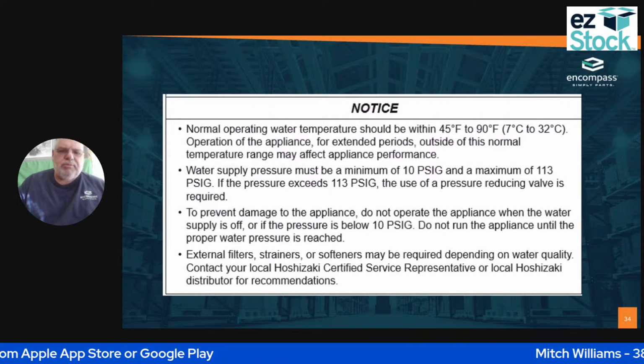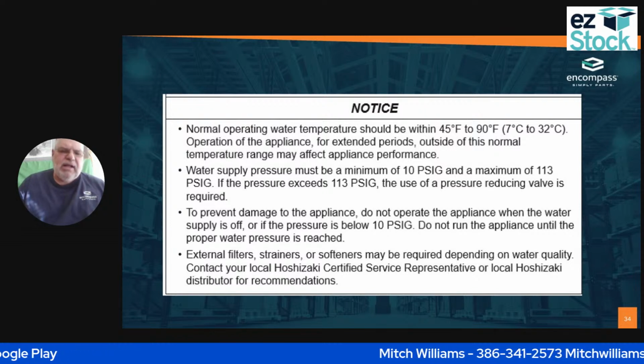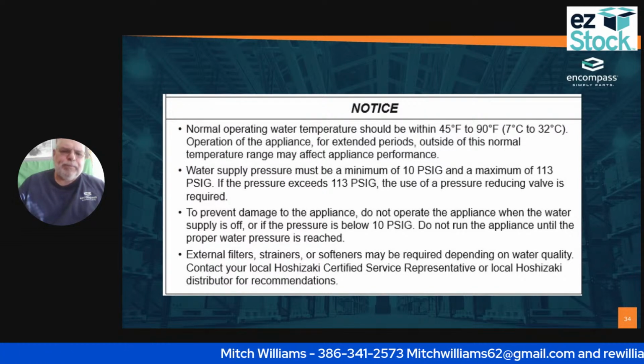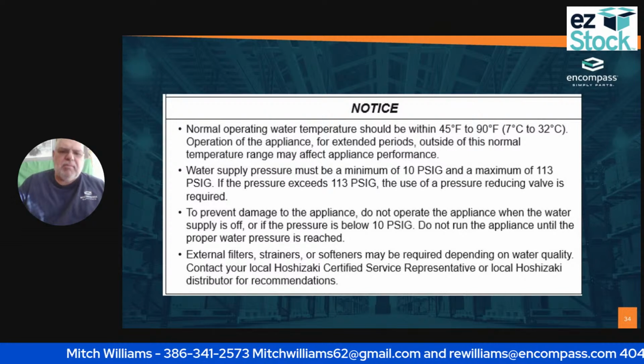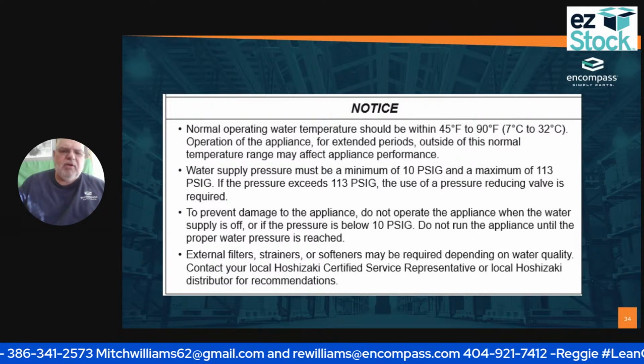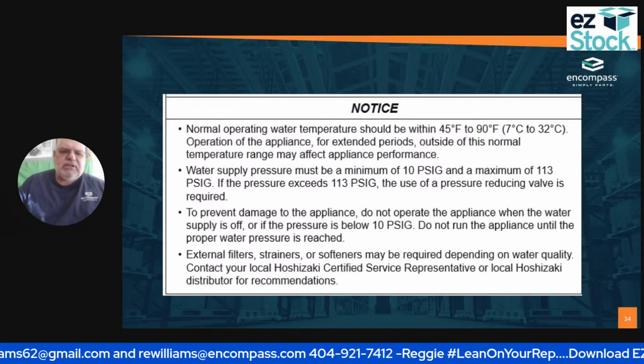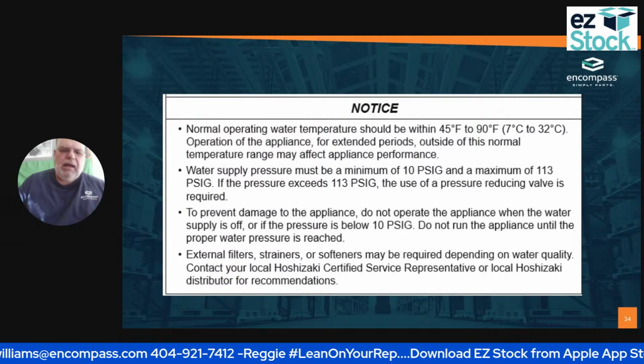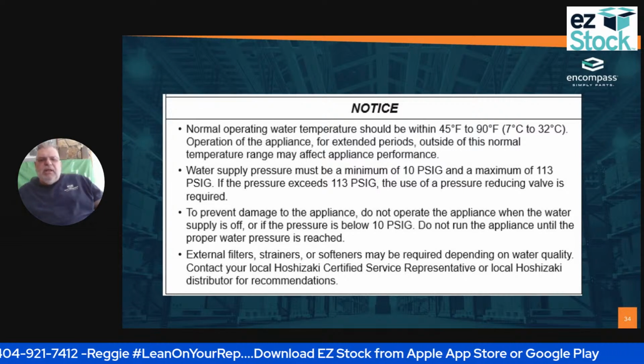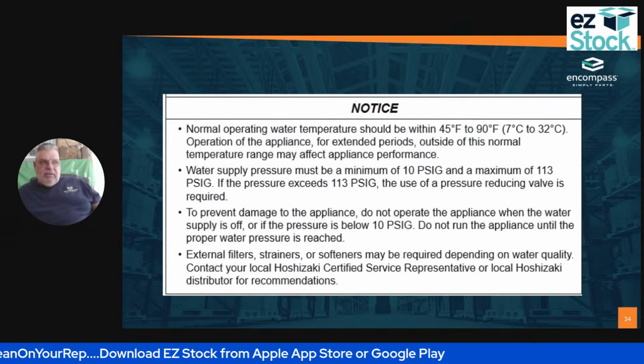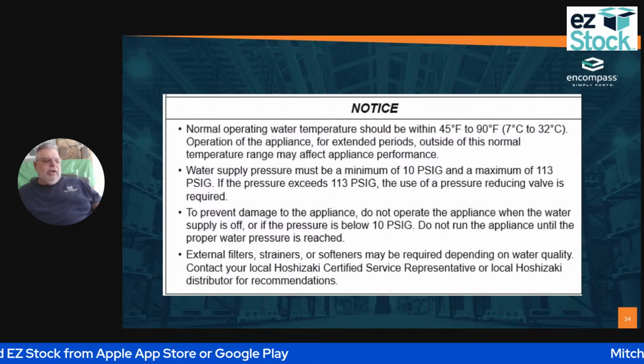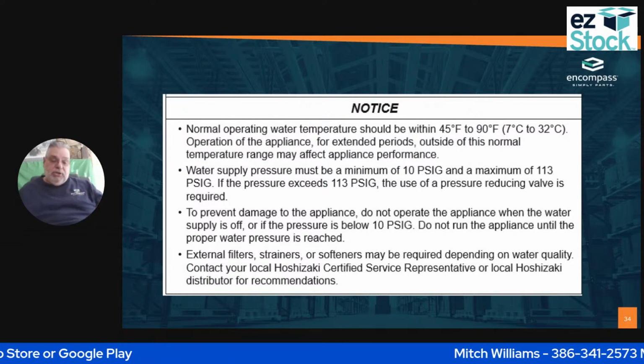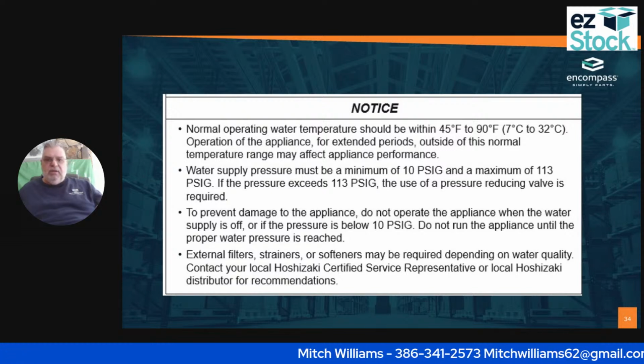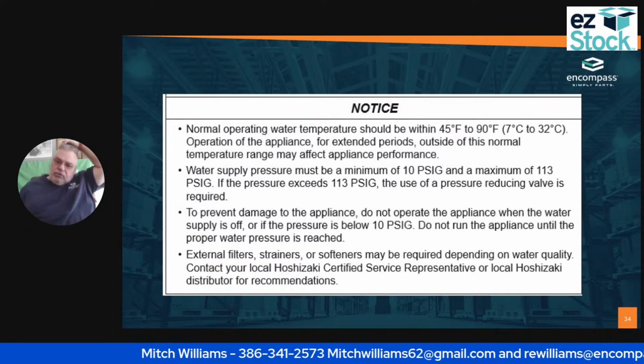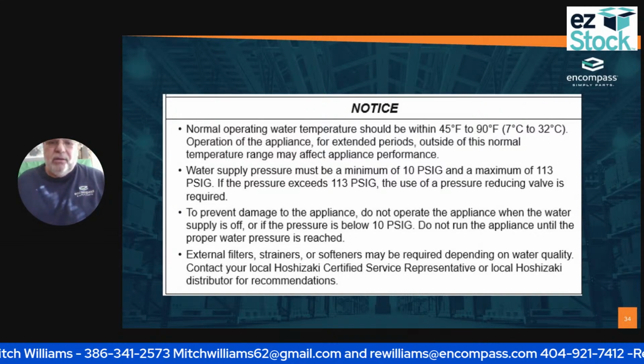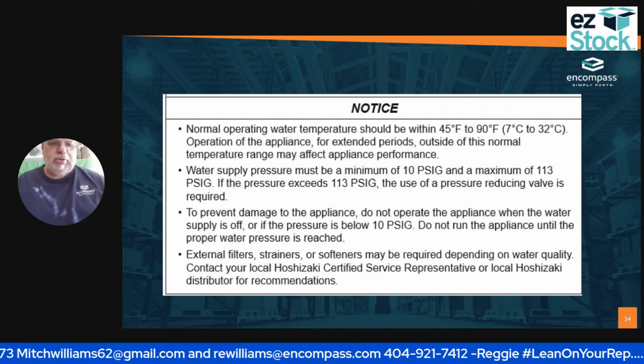Normal operating water temperature should be somewhere between 45 and 90 degrees. This goes for any ice maker. Okay. Water supply must be a minimum of 10 psi with a maximum of 113 psi. If it exceeds 113 psi, I'm going to need a pressure reduction valve. And you probably don't have that on your truck, but you're going to make sure, and that's for any ice machine. You're going to have to go and get one, or else if it's over 113 psi, it's going to leak. It's going to continue to let water in, and it gets worse and worse and worse.